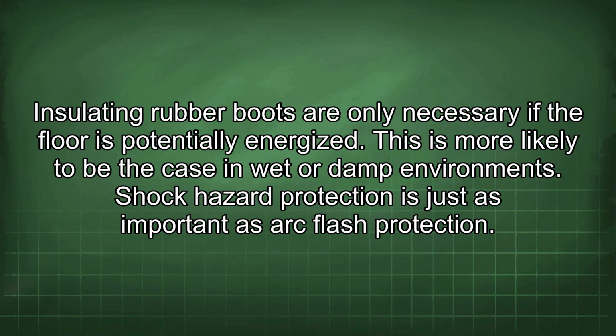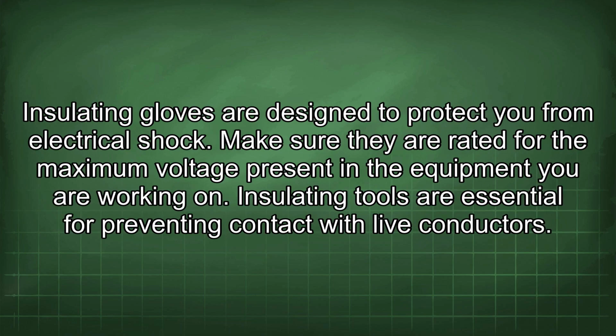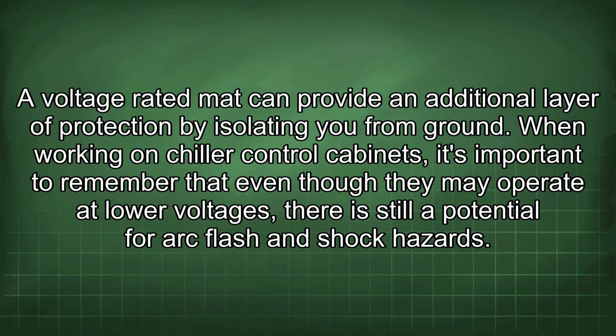Shock hazard protection is just as important as arc flash protection. Insulating gloves are designed to protect you from electrical shock. Make sure they are rated for the maximum voltage present in the equipment you are working on. Insulating tools are essential for preventing contact with live conductors. A voltage-rated mat can provide an additional layer of protection by isolating you from ground.